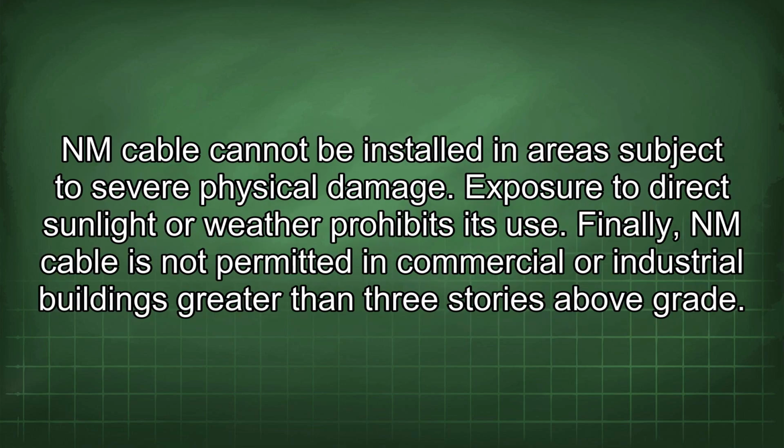NM cable cannot be installed in areas subject to severe physical damage. Exposure to direct sunlight or weather prohibits its use. Finally, NM cable is not permitted in commercial or industrial buildings greater than 3 stories above grade.